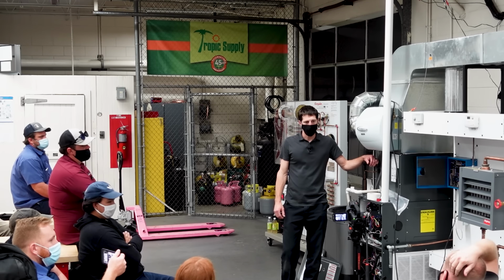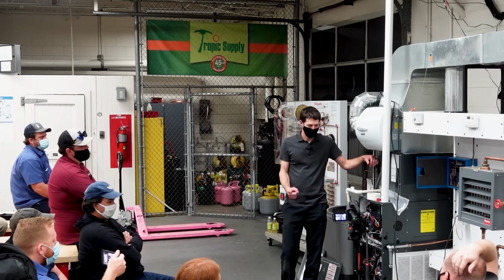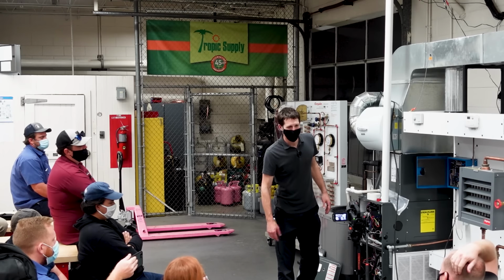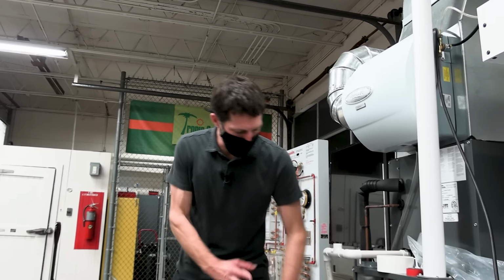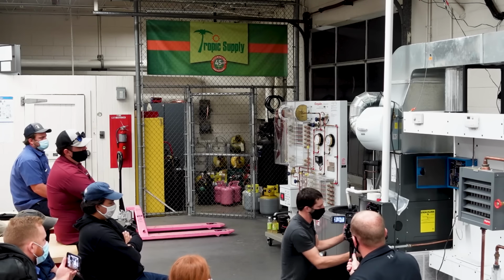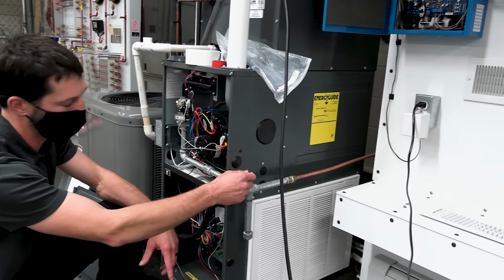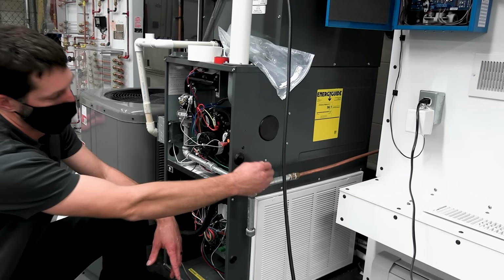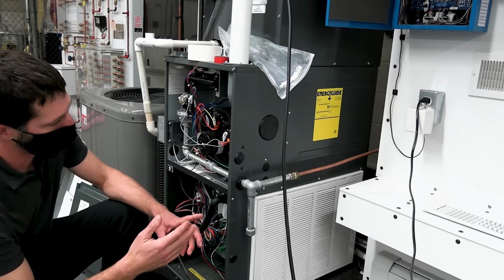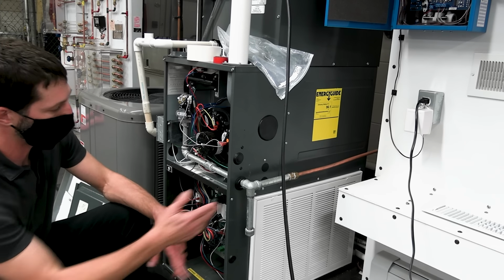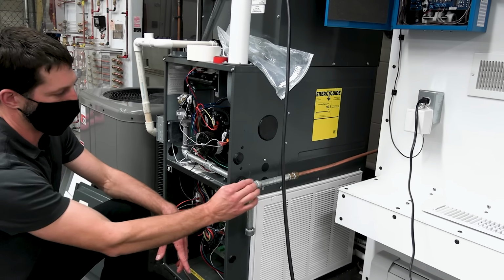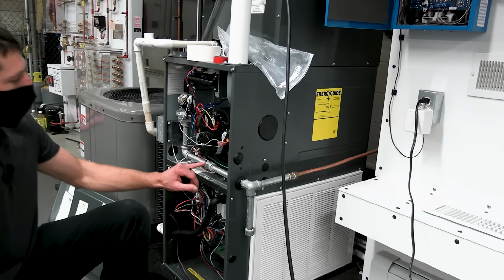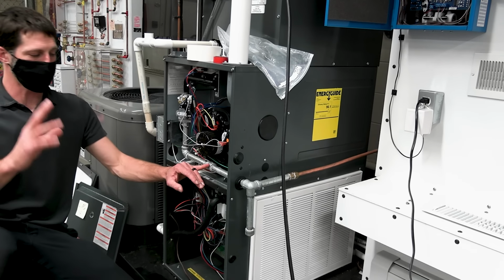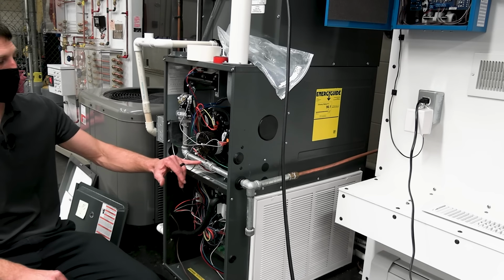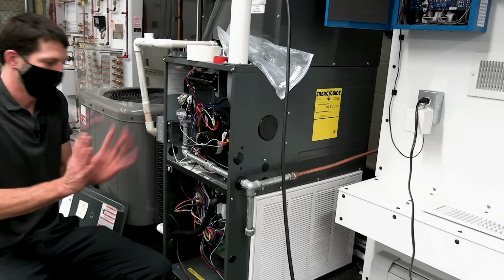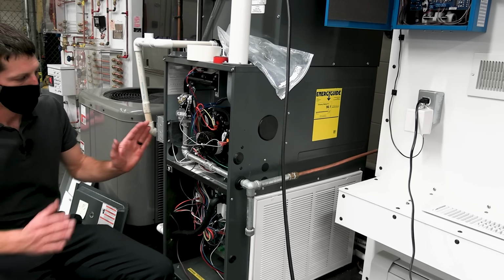Do you want to mention anything about the way that the gas is piped on this, for anyone who's going to comment on it and hammer it? So two things. One being that this is just a training unit, but you should have an off valve right here. And so basically there's several things. You want to have an off valve, and you're going to have a drip tee. And this is kind of an odd setup for the drip tee. Usually people that really take pride in the installation a lot of times don't use a coupling. Now that may hurt somebody's feelings or whatever, but you know, you can use.